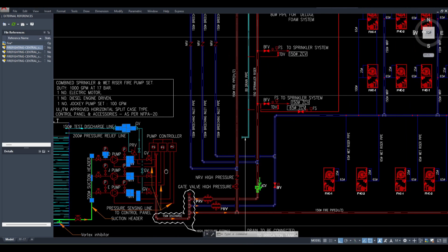What kind of building it is, how long you have to protect it, where it's situated, which city. According to that you select the running hours required. Then based on that, you see what system and load your pump is for, like whether it's designed only for hydrants, or for both hydrant and sprinkler. According to that you calculate the demand.